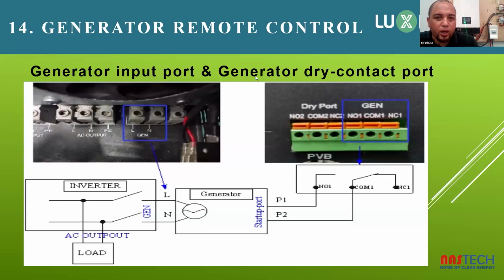Generator input port and dry contacts. So you have your live and neutral of your generator coming in, and then your dry contacts. As soon as your battery gets to a certain level, the normally open contact will close, and the inverter does that automatically for you. It will start up the generator, and then the generator will start supplying power to the inverter again.